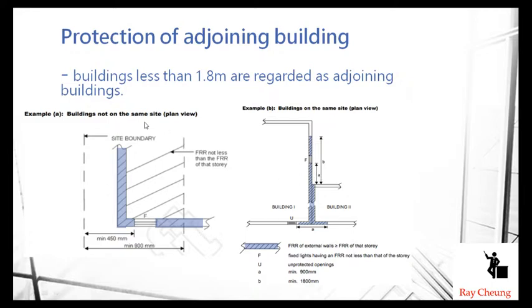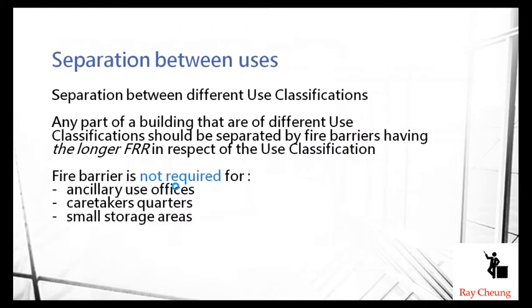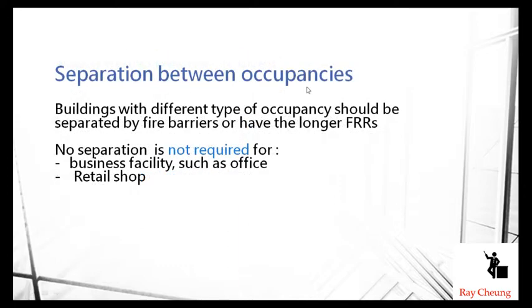If the building is not adjacent to another building but near a site boundary, the 900 millimeter requirement applies. Sometimes you also need to provide separation between areas of different use — for example, different classes of use require fire separation, although small storage areas may be exempt. Different occupancies may also need fire protection, though retail shops with good management and offices may not require this separation.